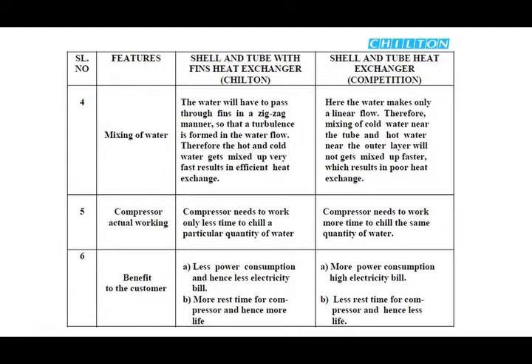Mixing of water, Chilton: the water will have to pass through the fins in a zigzag manner so that turbulence is formed in the water flow. Therefore, the hot and cold water gets mixed up very fast, resulting in efficient heat exchange. Competitor: here the water makes only a linear flow. Therefore, cold water near the tube and hot water near the outer layer will not get mixed up faster, which results in poor heat exchange.